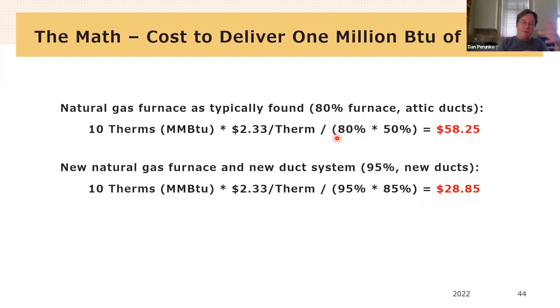And these are ducted systems, so after the piece of equipment, there's a distribution system. Typically you can do way better than this, but typically installed duct systems lose about 50% of the capacity of the conditioning that's pushed through them. So you have initial fuel, 80% efficiency of the equipment, so you lose 20% right there, and then 50% efficiency in your ducts, so you lose 50% of what came out of the machine. So it costs $58 per million BTUs of heat with an 80% furnace and sort of typical ducts in an attic.